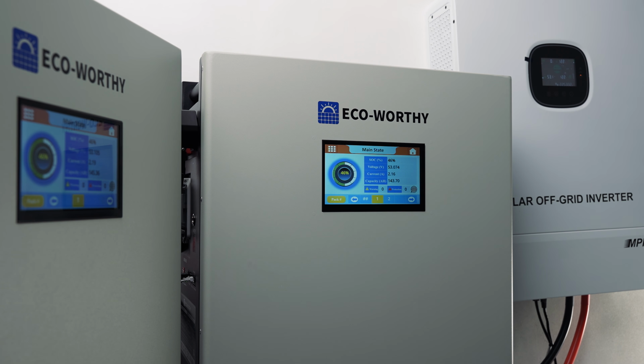Remember, you can connect up to 15 of these units. The batteries need to talk to each other and the inverter to manage the charge properly. The first battery needs to be set up as the master, usually ID1, and the second one as its slave, ID2, using the small switches on the side panel.